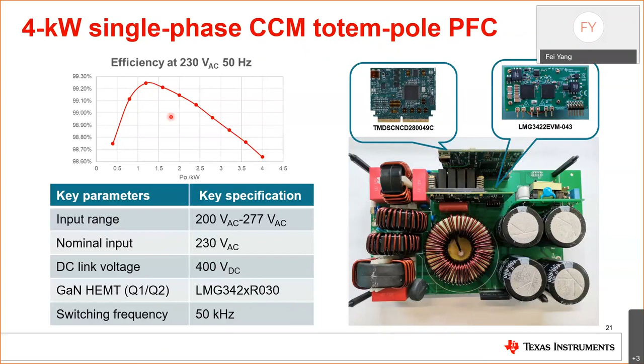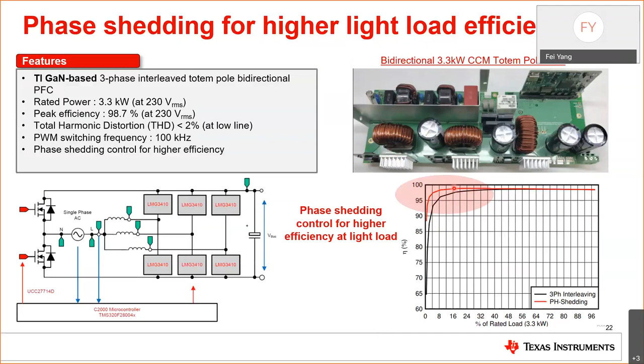In this slide, I'm showing another design. This design is a 3-phase interleaved PFC, which can still achieve 3.3 kilowatts full power. The interleaved design gives you flexibility to control the power and also optimize the losses at light load. You have the option to turn on all three FETs at light load. However, you can also do phase shedding, which means you turn on one or two interleaved phases to help improve the system efficiency at light load. This is experimental data, and by doing the phase shedding, the light load efficiency can be greatly improved.